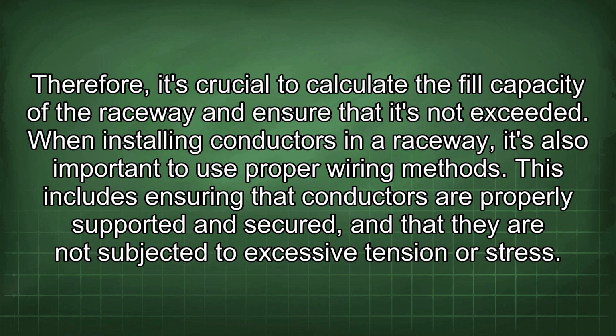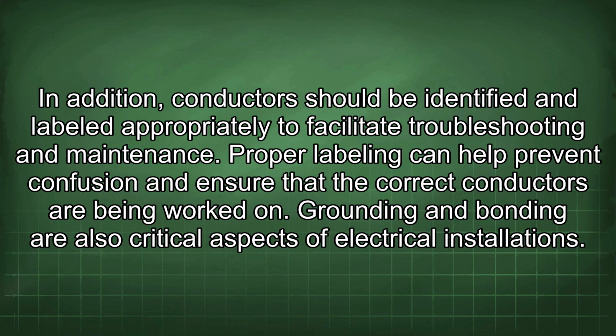When installing conductors in a raceway, it's also important to use proper wiring methods. This includes ensuring that conductors are properly supported and secured, and that they are not subjected to excessive tension or stress. In addition, conductors should be identified and labeled appropriately to facilitate troubleshooting and maintenance. Proper labeling can help prevent confusion and ensure that the correct conductors are being worked on.